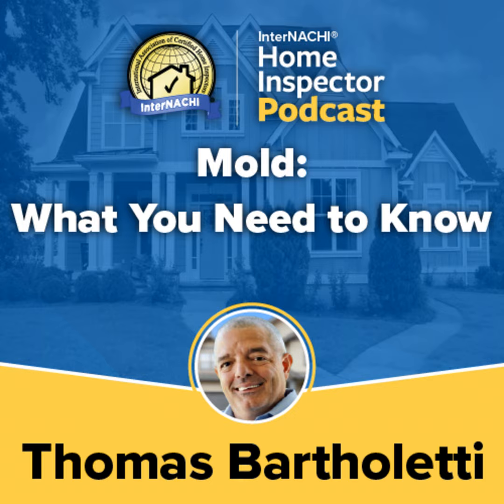What I want to get to is that air filters are rated according to their minimum efficiency reporting value, MERV value. Most home filters range from 4 to 13. A MERV 4 is typical because it's cheap and inexpensive, but it really just keeps big dust particles off of the equipment, and that's it. MERV 13 is kind of above, and I think MERV 12 is hospital range. I recommend a MERV 12 at least, because it really creates a lot of filtration of your bacteria and your mold spores and so on. So I'd really recommend a MERV 12.